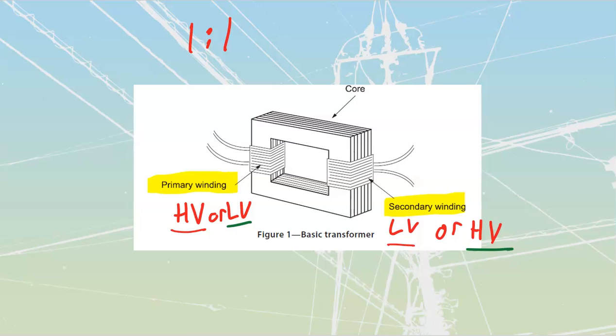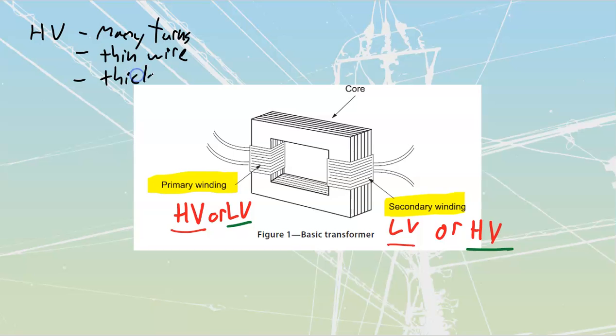The high voltage winding and low voltage winding are identified in construction. The high voltage winding is going to have many more turns. They're going to be thin wire. So HV is going to have many turns. The wire itself is going to be thin because the higher voltage side carries fewer amps. It's at a higher voltage, therefore it's going to be smaller, less amps. Thin wire. And it's going to have thicker insulation. Thick insulation.